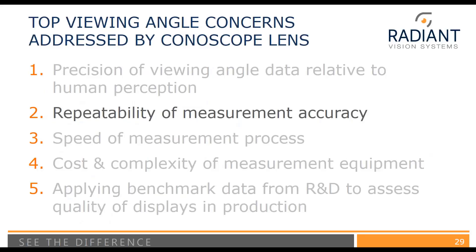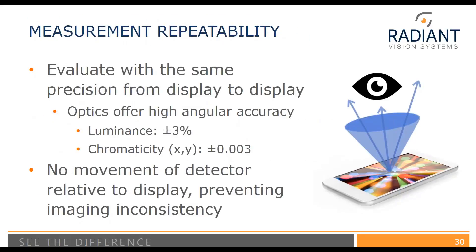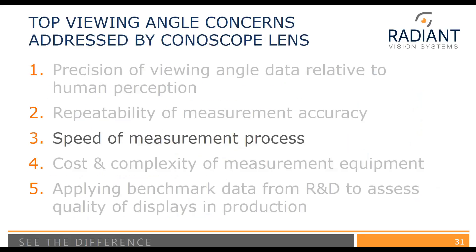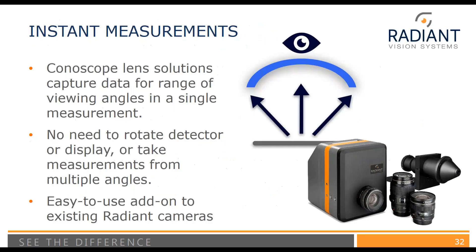How to get repeatability of measurement accuracy? Instead of using a robot, multiple spot colorimeters, multiple two-dimensional measurement devices, or moving the detector relative to the display, you can use a colorimeter with the Conoscope lens and alleviate all of those problems — because there's no movement between the measurement device and the DUT. For speed, using a Conoscope lens you can measure luminance data from multiple viewing angles with a single measurement. There's no need to rotate the detector or the display, and the Conoscope lens is an easy add-on to existing Radiant Vision Systems cameras.